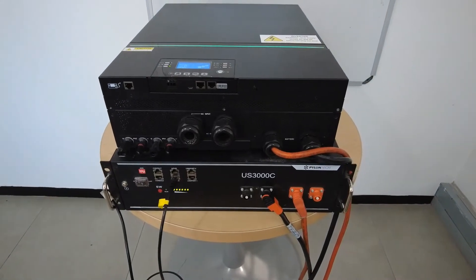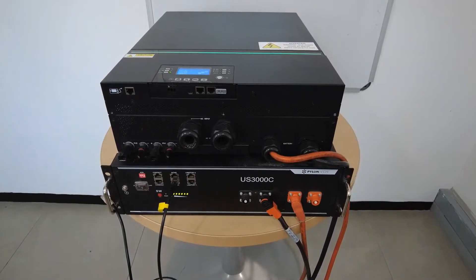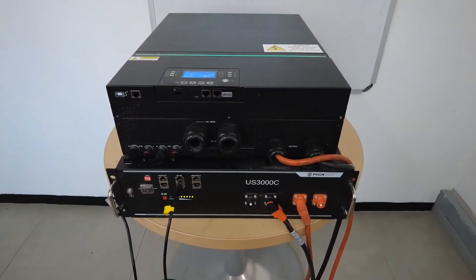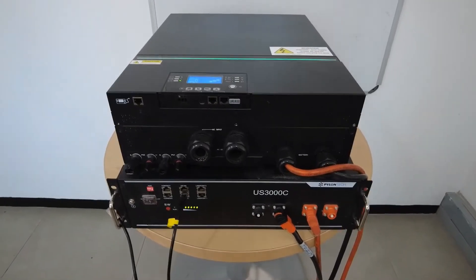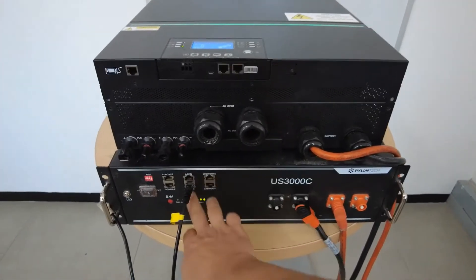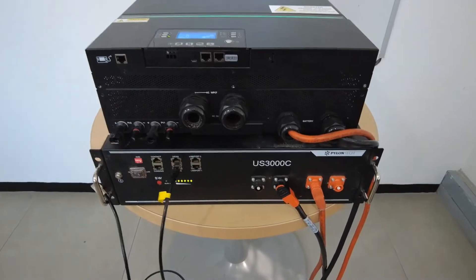A common complaint is that the Pylontech C-type batteries do not communicate with the RCT inverter. The reason is that the previous generation US3000 model battery had a different RS485 pin layout, which Pylontech changed with the C-type.